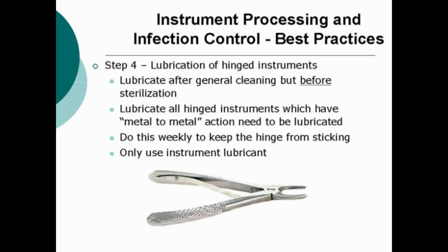Step 4. The lubrication of hinged instruments. Lubricate after general cleaning but before sterilization. You want to lubricate all hinged instruments which have metal-to-metal action. Do this weekly to keep the hinge from sticking, and only use instrument lubricant.